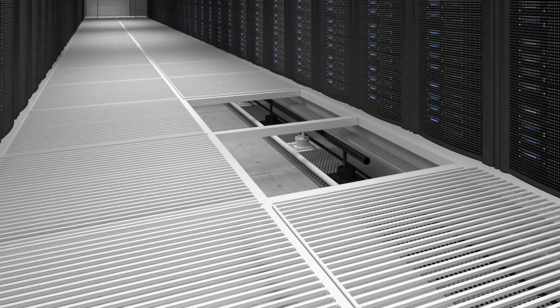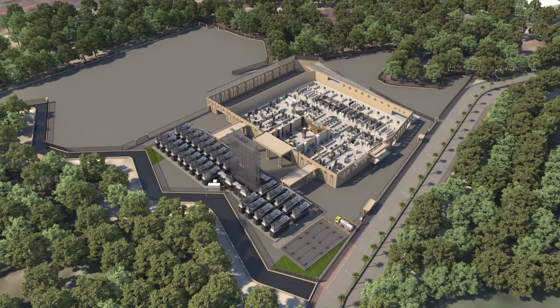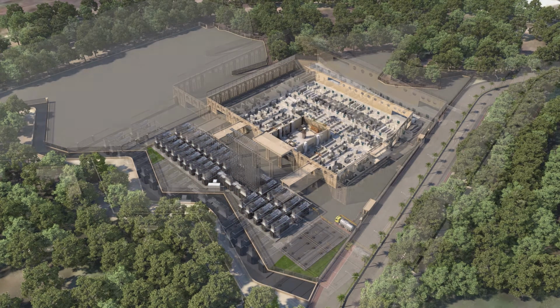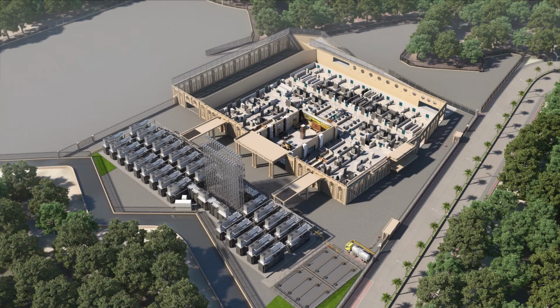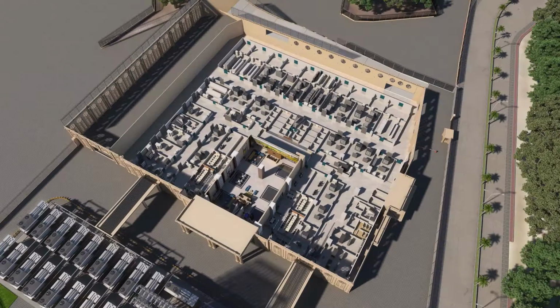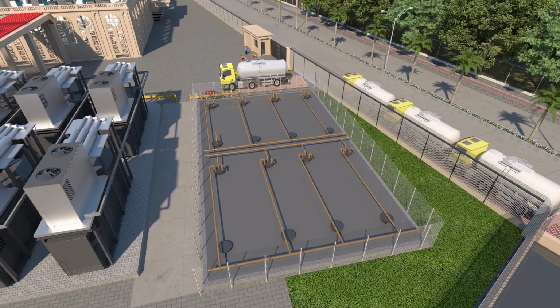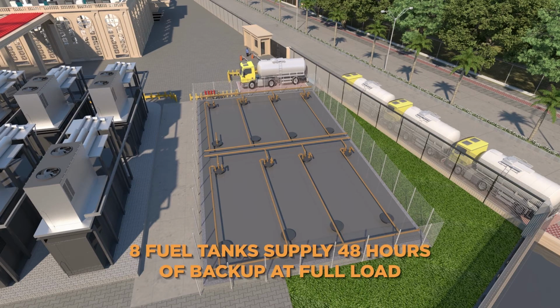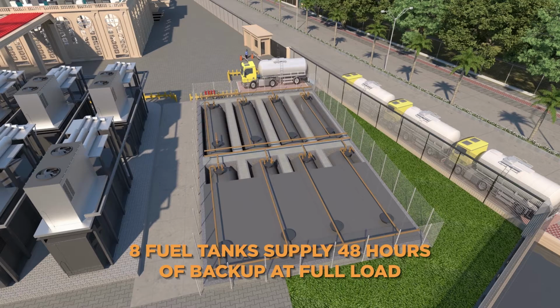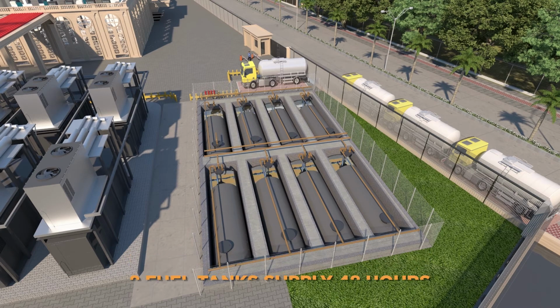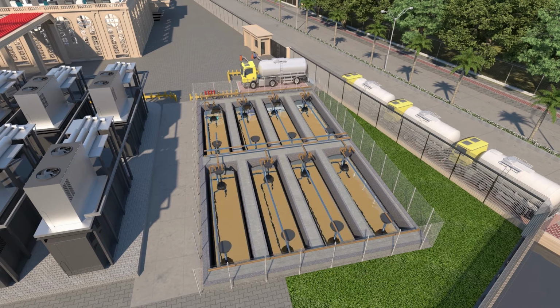The utility feeder is backed up by an array of 32 diesel generator sets, each of 2.25 megawatt in N plus 2 configuration that supplies continuous backup power to the data center through an array of specially designed fire and water-resistant bus ducts. The diesel generator sets are backed by 600,000 liters of diesel fuel stored in underground tanks, ensuring 48 hours of uninterrupted operations at full load.